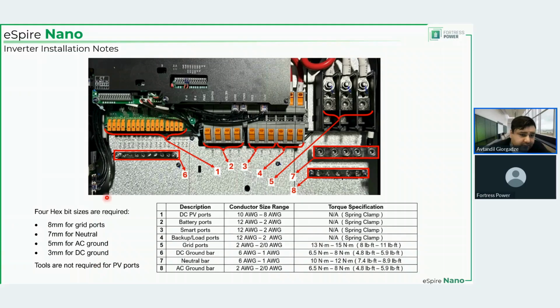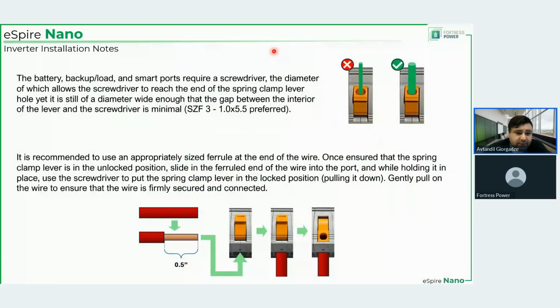And also, here are the tools that you're going to be using. So what do I mean by spring clamps? In this position, the clamp is open, and you can slide in the cable. The cable must have 0.5 inches of exposed conductor when going in, and once you slide in the exposed conductor, you hold it in place, put in a screwdriver, and again, this shows you what is a better way. The screwdriver should reach all the way to the end of the hole, and should be almost the same diameter as the hole itself, so that you don't break the side of this plastic right here. So you hold the cable in place and you lock the conductor in place, and that's about it. No need to torque anything down.